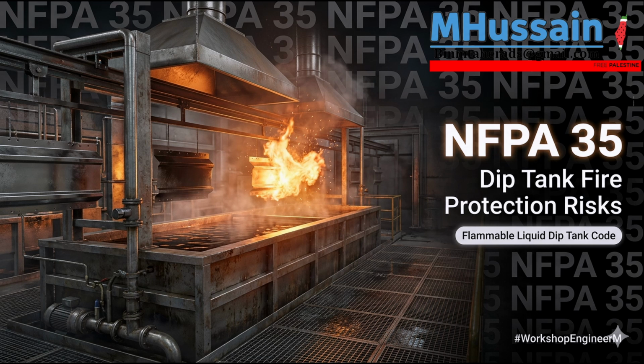Now let's talk about the physical pipes themselves. The standard dictates they must be made of steel or other approved ductile materials, but here is the massive red flag, the absolute prohibition. Cast iron valves, fittings, and pipes are strictly prohibited. Banned entirely. I really want to dig into the why here, because cast iron has been the backbone of global plumbing for over a century. Why ban it here? It comes down to the metallurgy and the carbon content of the metal.